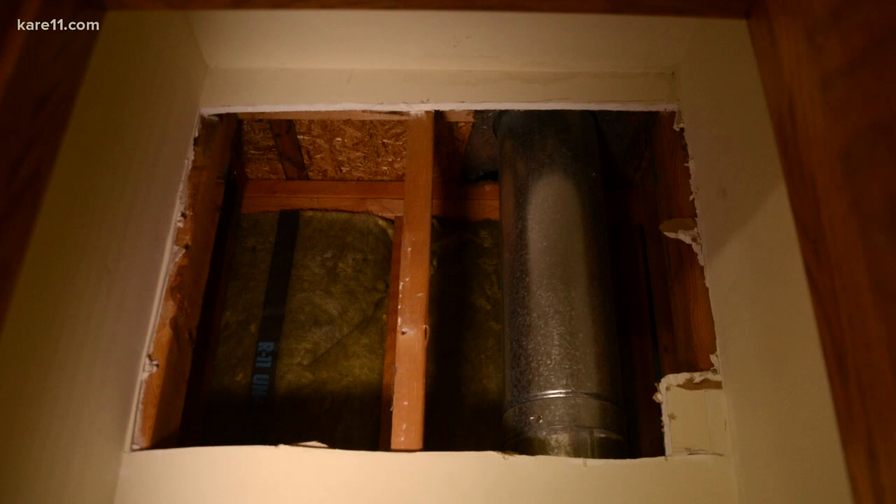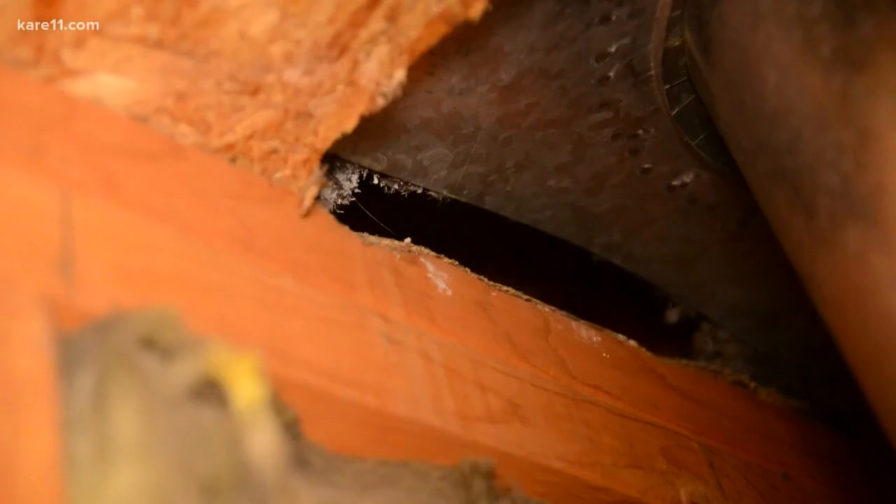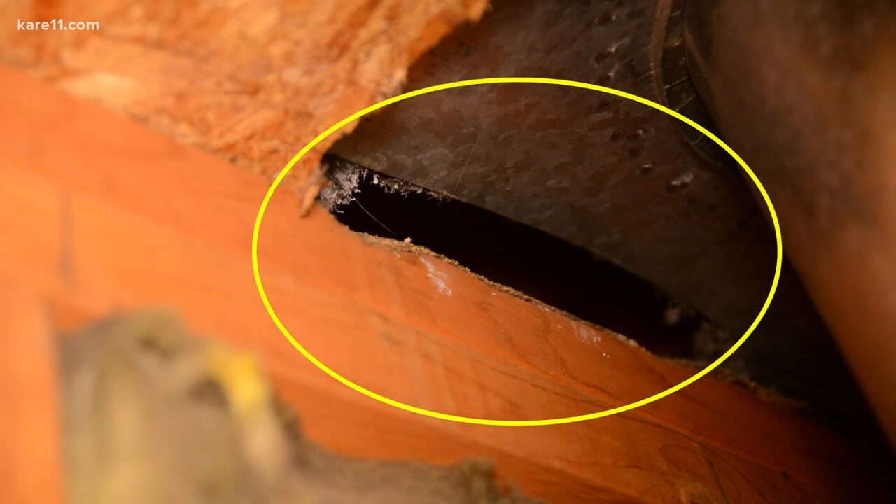In addition to the ventilation issues, this house had an older water heater — it was naturally vented, meaning warm air just rises up through it. That warm air and that pipe were going into a bad spot of the attic, causing a lot of snow melt on that roof. Then it freezes, creates a dam, water gets to it, and actually starts to get into the attic.